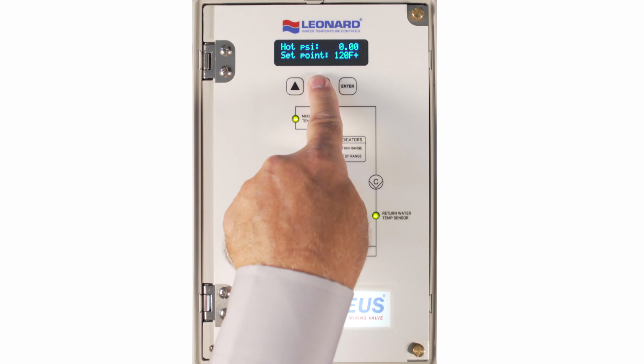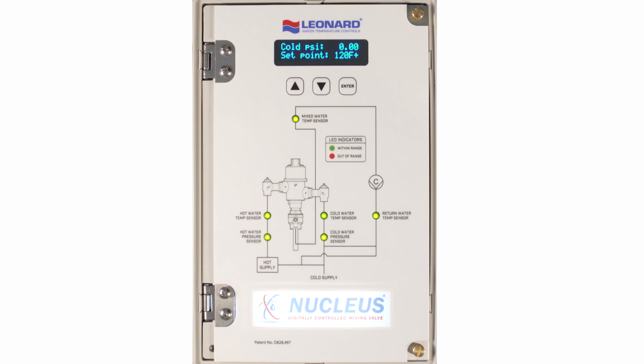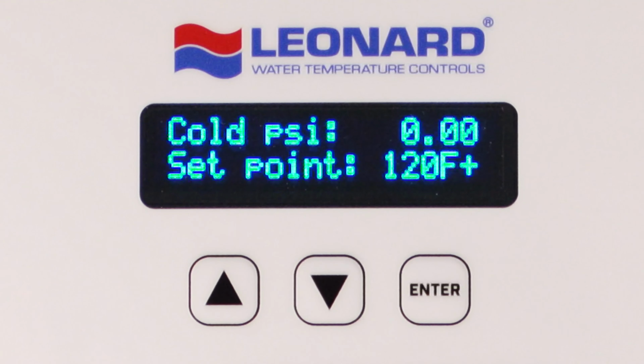Menu screen 5. Inlet cold water pressure. Pressing down 5 times displays cold PSI. This indicates the inlet cold water supply pressure, PSI, available to the mixing valve if the Nucleus is so equipped with the optional pressure sensor, P2. Note: a large negative value displayed at the cold PSI line is an indication that there is no sensor installed to the main control board, or the wiring to the main board is improper, or the sensor is damaged.